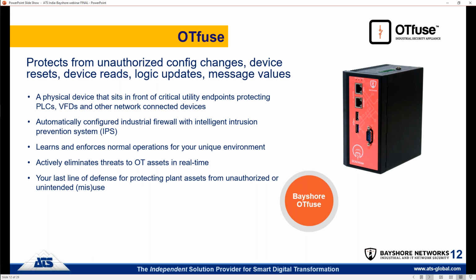That goes back to read-only, read-write, programming. You generally don't want full programming access from devices that don't absolutely need it—that's an excessive level of permission and access compared to what the business need should be for that device relationship. But you also want a very easy way to change that if there's a temporary maintenance requirement or a scheduled update or something else.